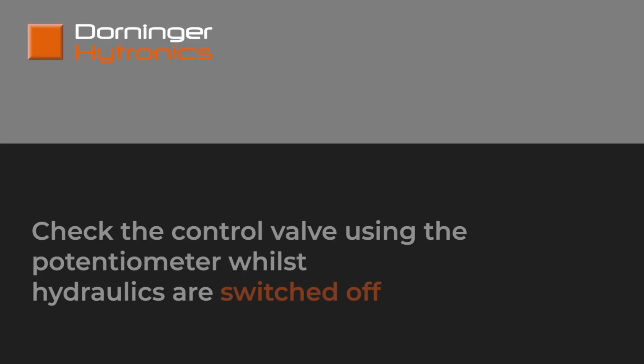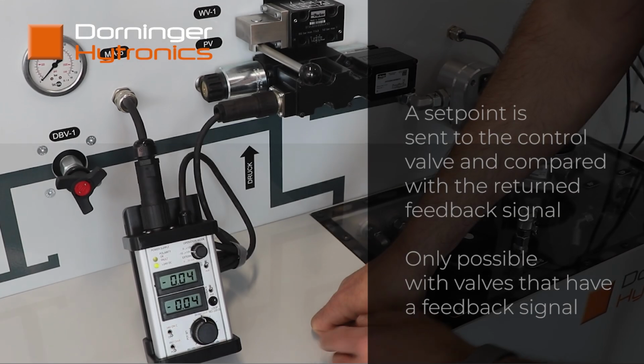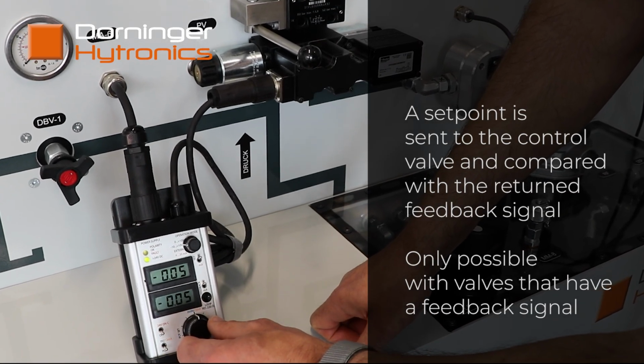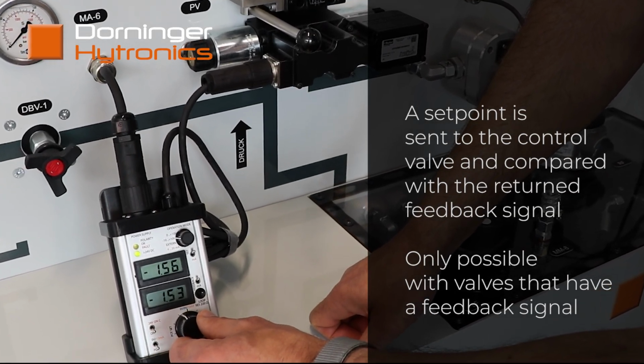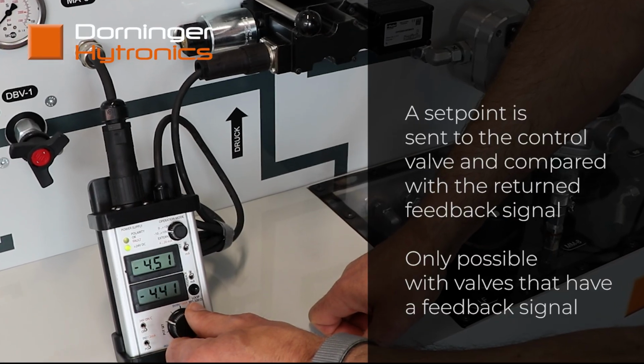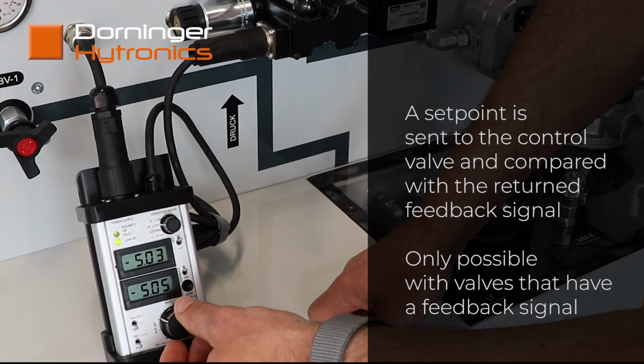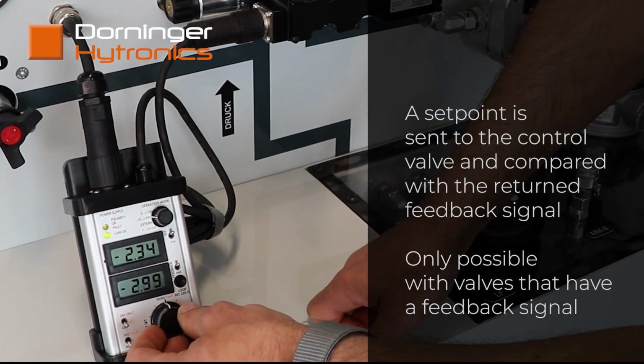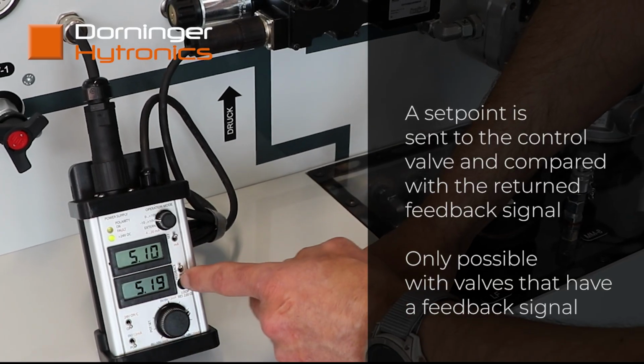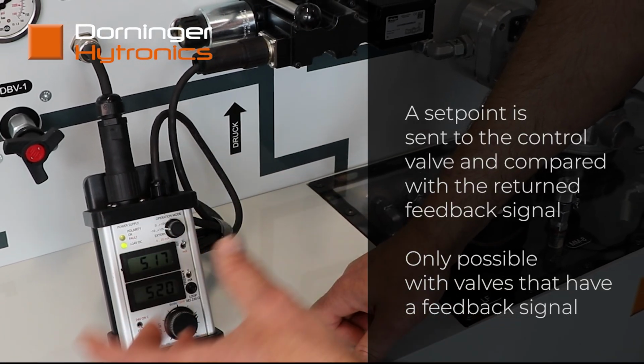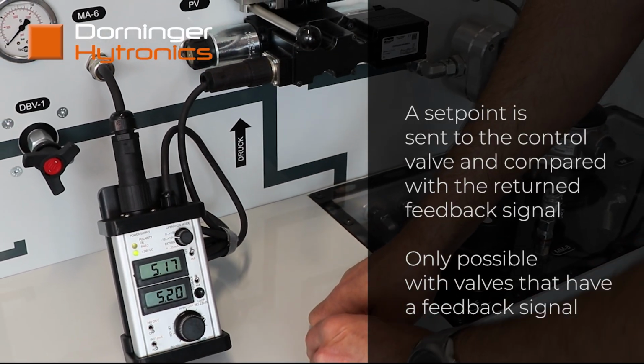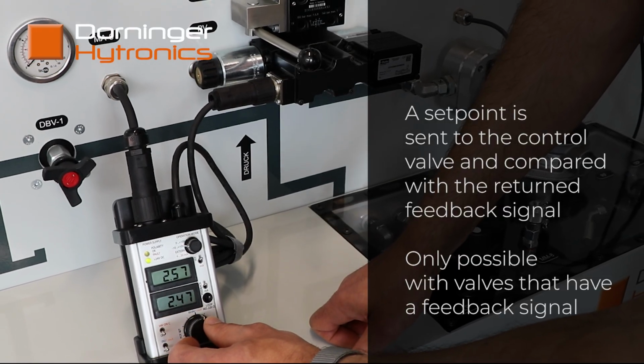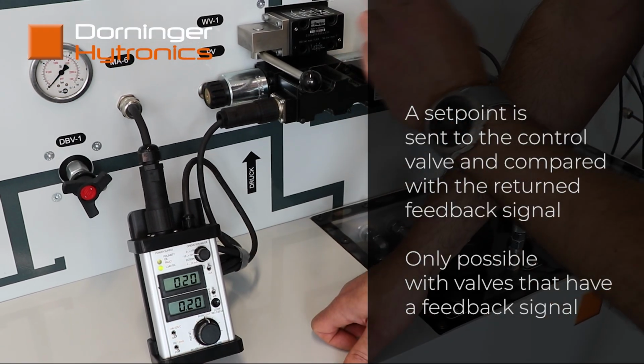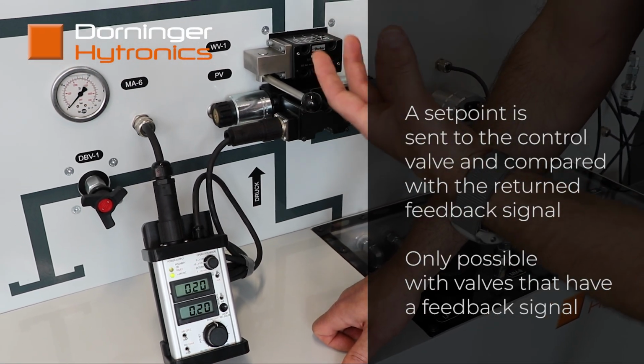We can now move the spool inside the control valve using the potentiometer. This test is carried out without a hydraulic supply and is only possible with directly operated control valves that have a feedback signal. According to the data sheet, we have selected plus or minus 10 volts for the setpoint signal and the feedback signal. We can now use the potentiometer to control and move the spool inside the valve in a targeted manner. The feedback signal tells us the position of the spool.